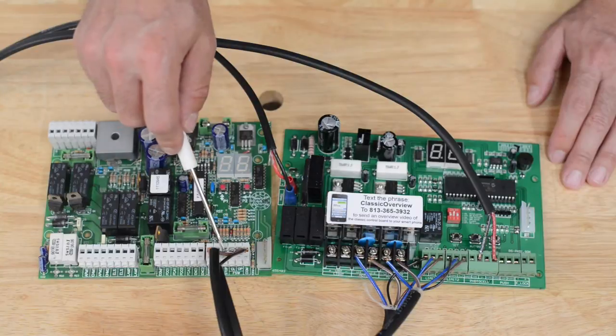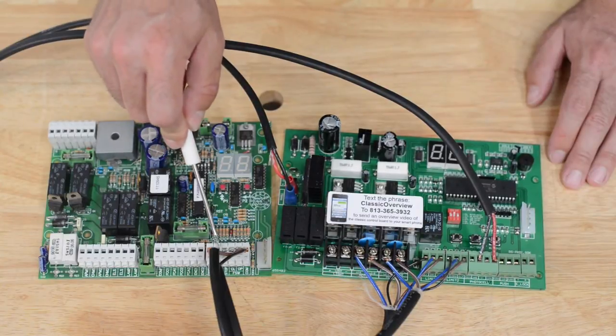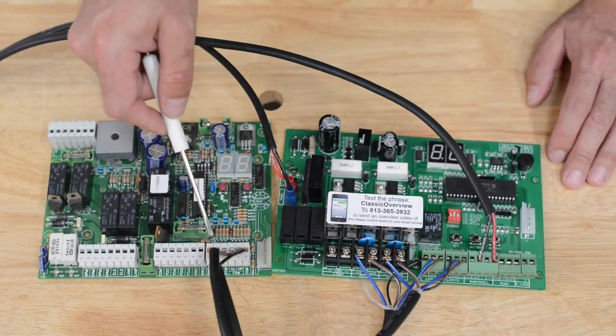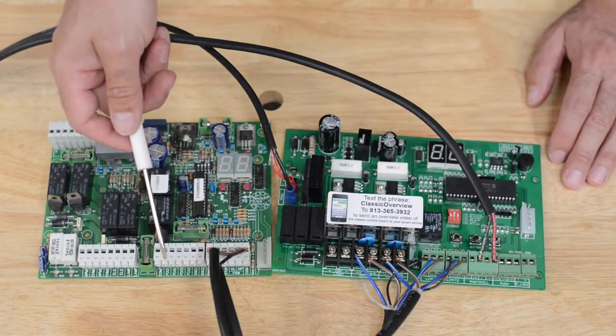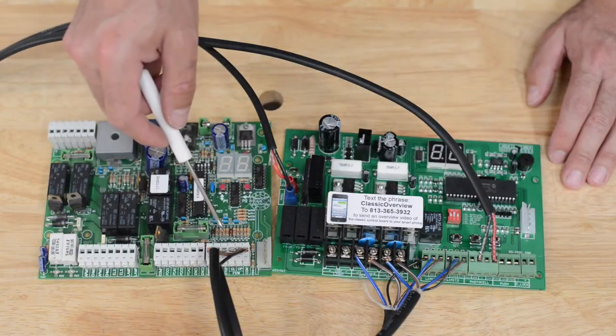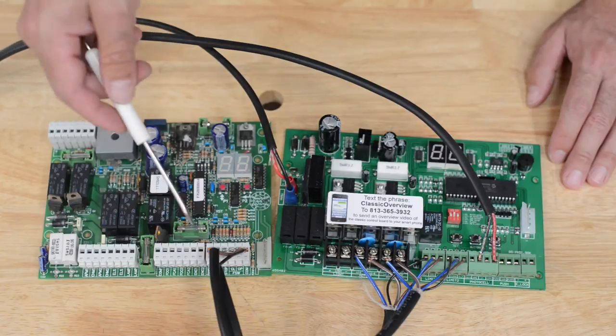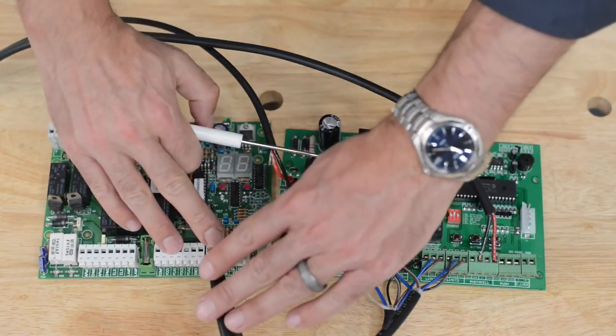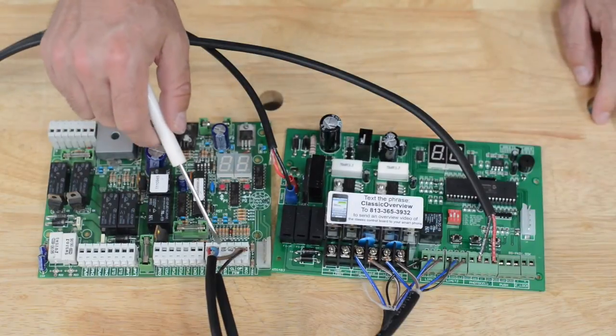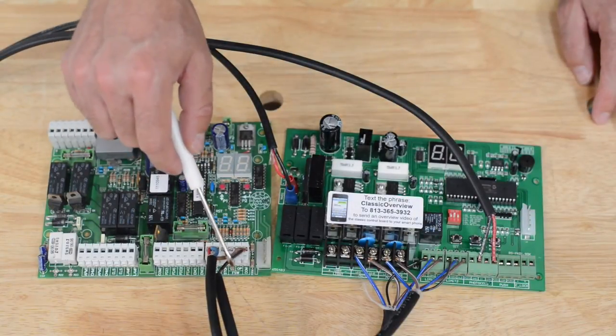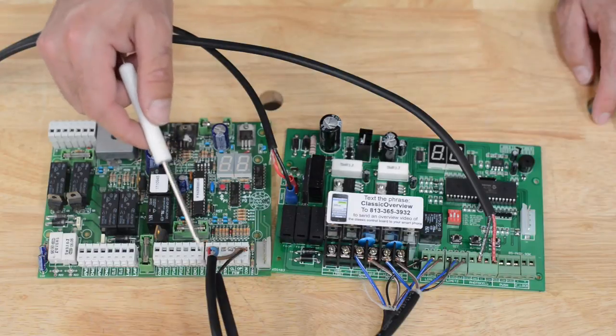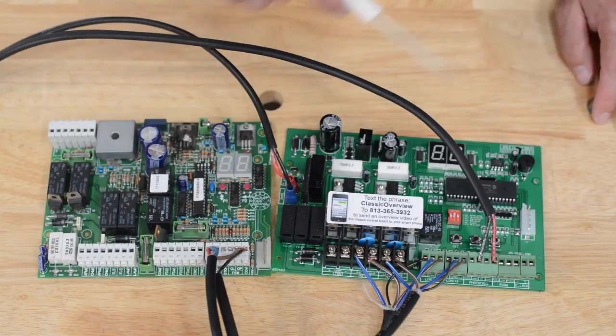Lastly, we have the accessory block. This is the CN4 block. This is where you would have devices like an exit sensor, a push button, photo eyes, things of that nature. On this setup, we have our safeties jumped out, like the majority of the customers that we have do. And we have a push button, which is our red and black wire. And then we have the leads from the exit sensor, which is our blue and brown wire.